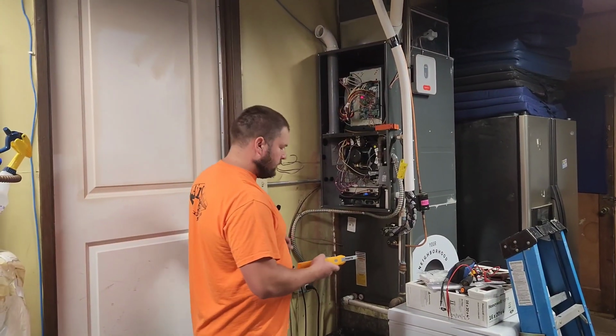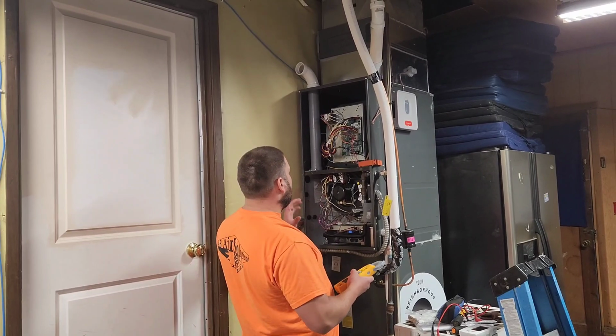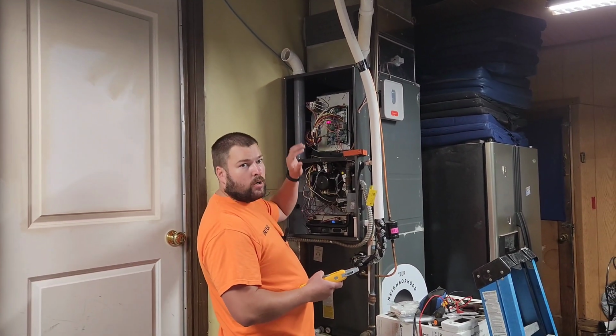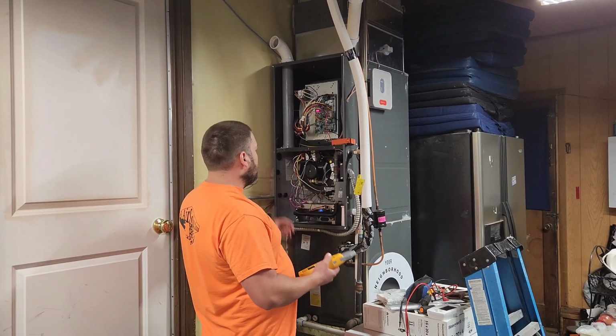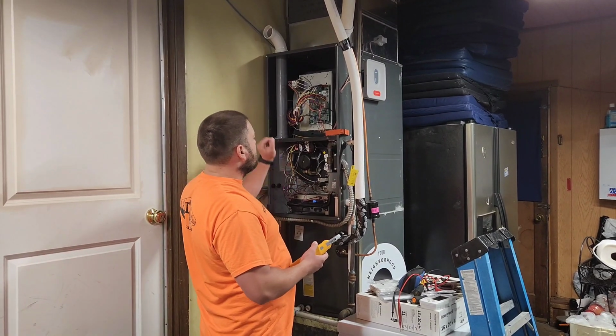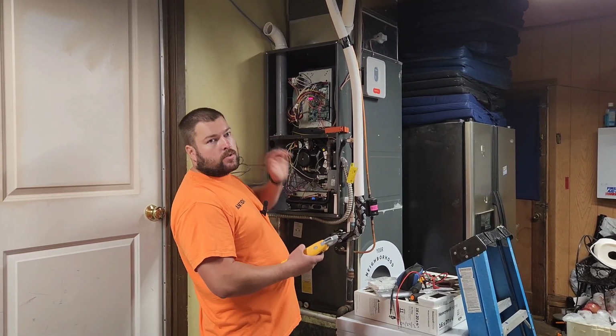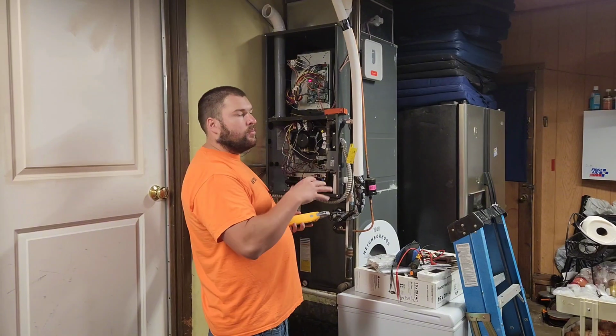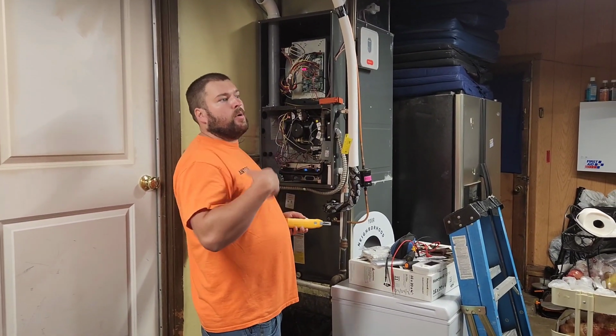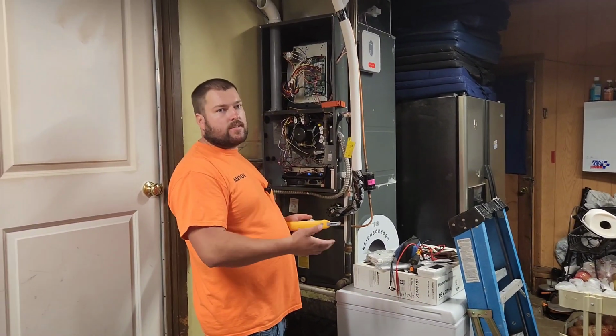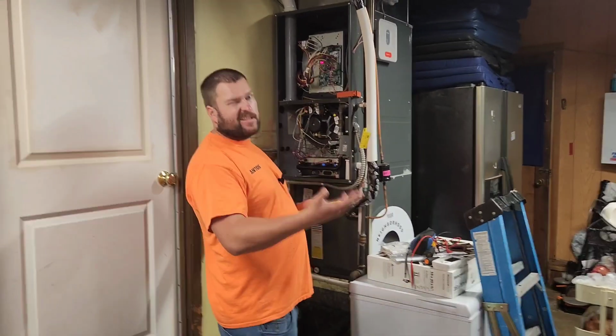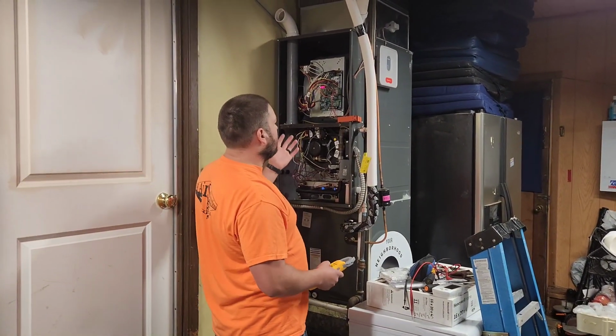Okay, so with the furnace running, now that our inducer motor and our blower motor are running, we'll check amps on the inducer motor and the blower motor. We just want to see that the motors are not pulling too much amps during startup and while they're running, because that's a sign that the motors are failing. So that's just something we'll check during preventive maintenance.